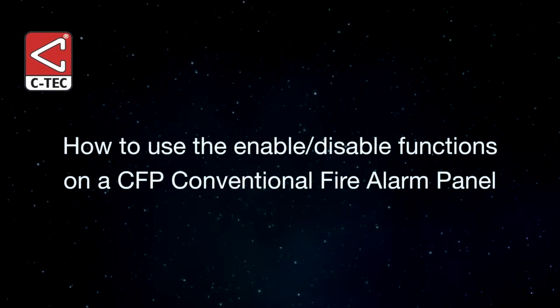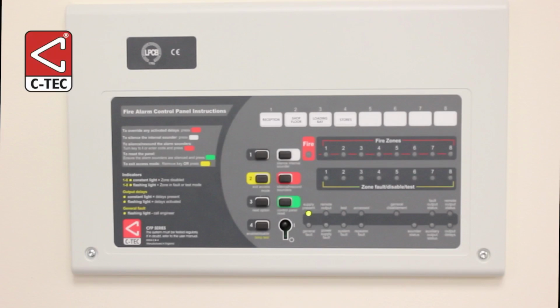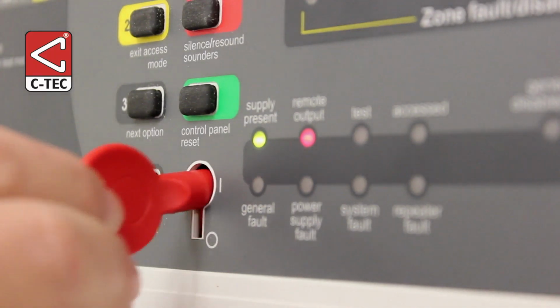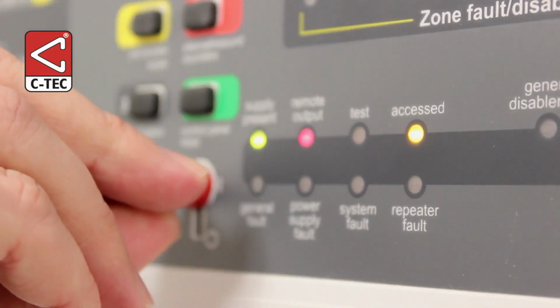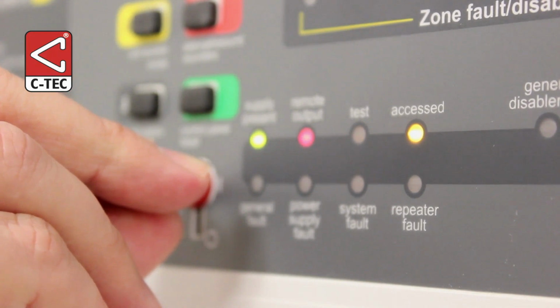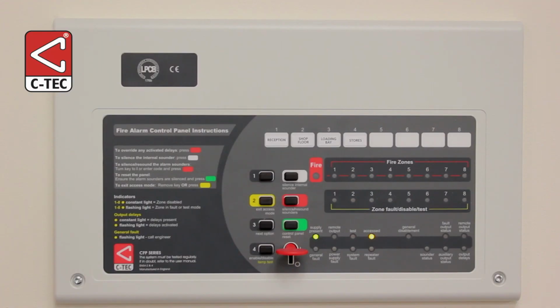How to use the authorised user controls on one of C-TEC's CFP fire panels to enable and disable zones or other functions. To gain access to these controls, you must first put the panel into access level 2. You can do this using one of two methods: entering a secure code using the panel's keypad or turning the key switch. The access light will turn on to indicate the authorised user controls are operative. You can enable and disable functions you require using a simple selection process.